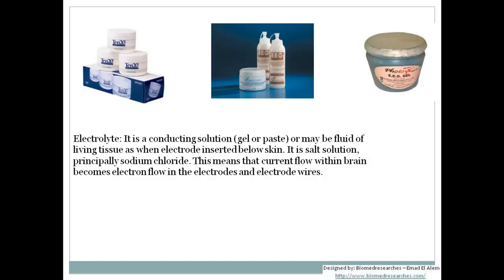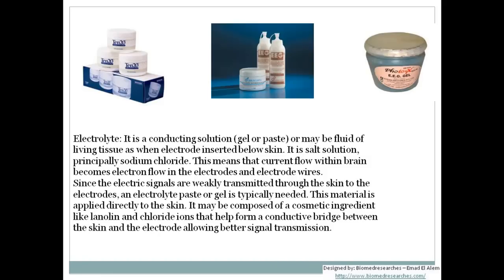The electrolyte ensures that current flow within the brain becomes electron flow in the electrodes and electrode wires. A very common paste used is the Ten20 paste, widely used by many manufacturers as a conductive solution. Since electrical signals are weakly transmitted through the skin to the electrodes, an electrolyte paste or gel is typically needed. The material is applied directly to the skin and may contain ingredients like lanolin and chloride ions to form a conductive bridge between the skin and the electrode for better signal transmission.